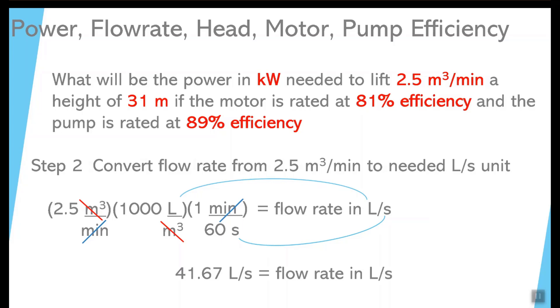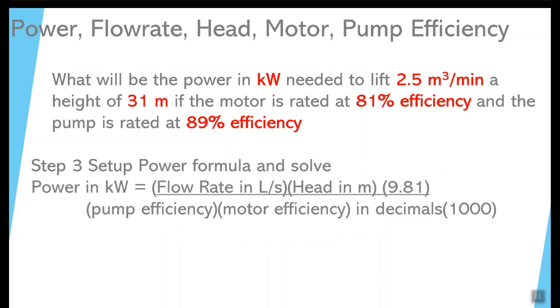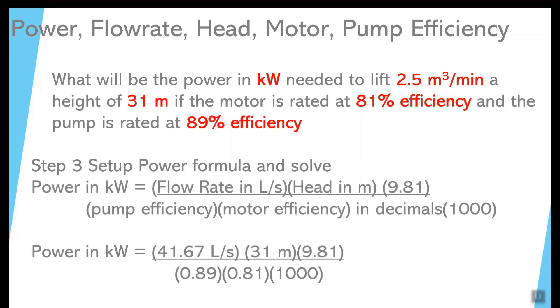Now plug that answer into the formula. Power in kilowatts equals 41.67 liters per second times the head of 31 meters times 9.81, divided by the pump efficiency of 0.89 times the motor efficiency of 0.81, divided by 1,000. The final answer is approximately 17.58 kilowatts.